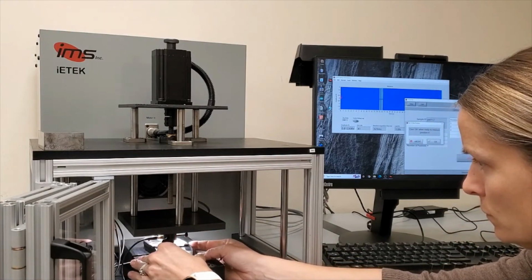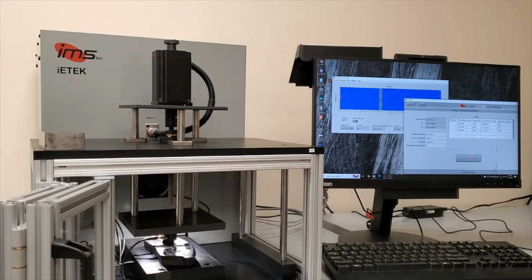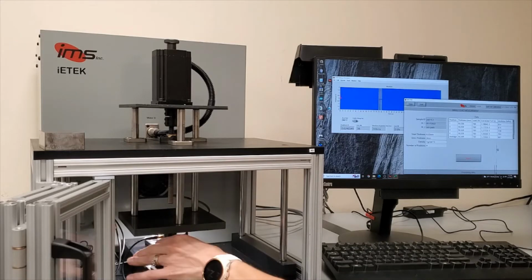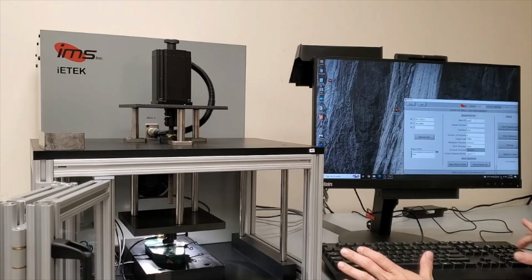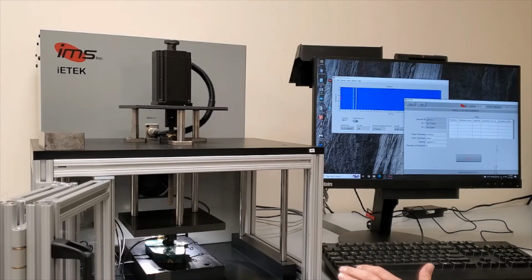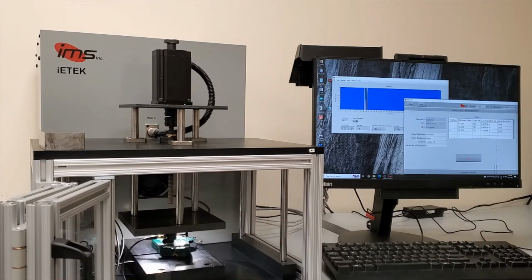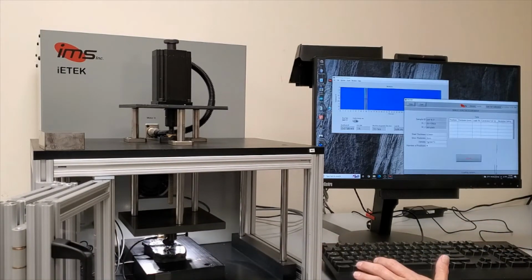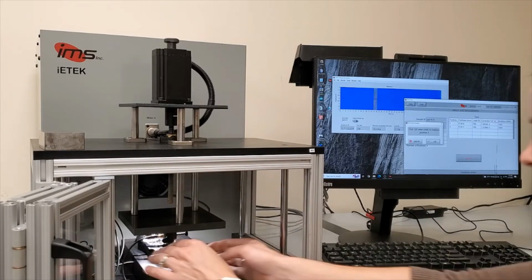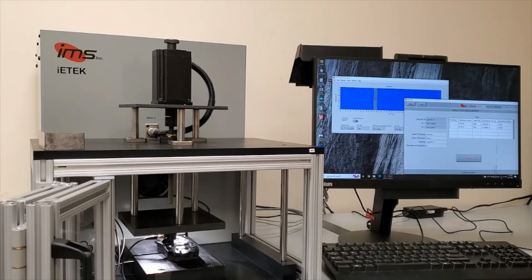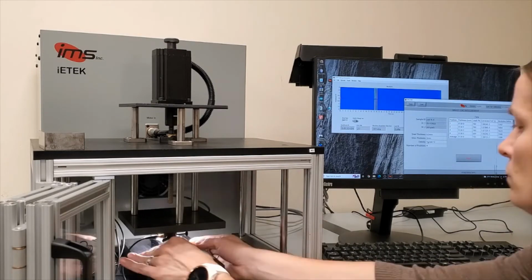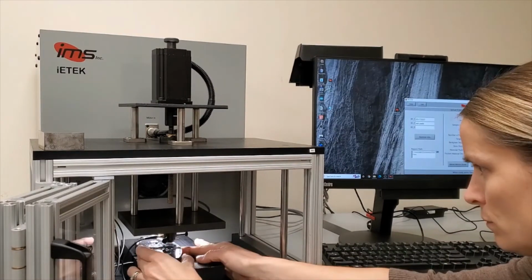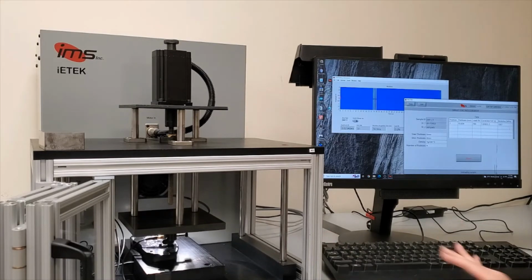I'm going to speed this up a little bit so that we can get through all of this. We're going to measure a total of 5 different pads, and I wanted you to be able to see how that goes. Now, the actual measurement process, once the preload has been put in place, is actually quite fast. It takes less than 300 milliseconds to actually make the measurement.